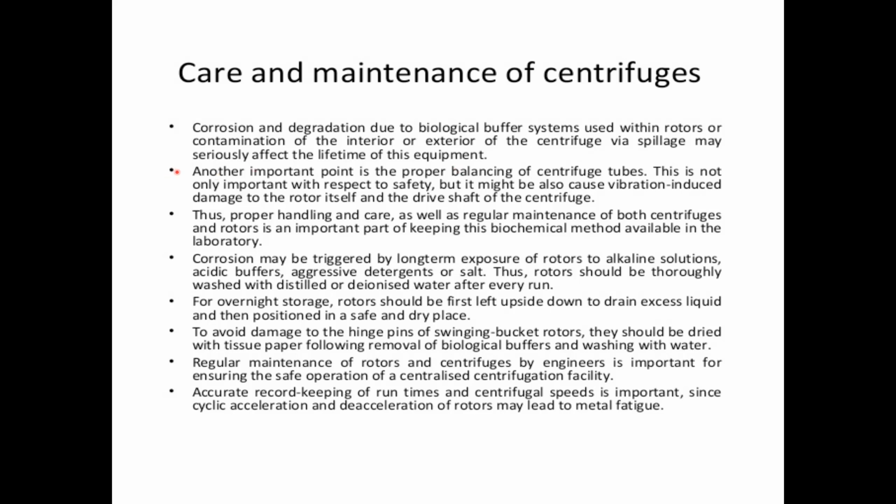Another very important point is the proper balancing of the centrifuge tubes. This is important for safety, but when the centrifuge tubes are not properly balanced, it might cause vibration-induced artifacts and damages of the rotor itself, and the spindle where the rotor is resting on.